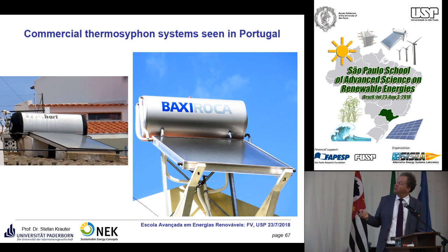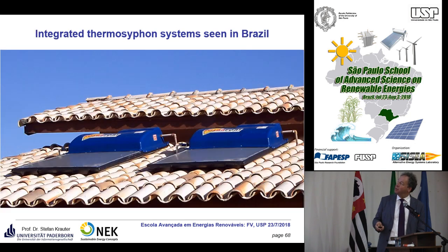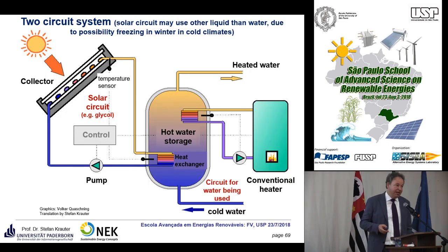Because the buoyancy of the heated water is very low, the storage always has to be very close to the collector. This led to a system in Brazil that's typically integrated, so you integrate the storage almost inside the collector. This is not possible in many countries because it's freezing in winter. If it freezes, you cannot use the water you're using for showering directly. You have to have different media rather than water, for example glycol, something like this.